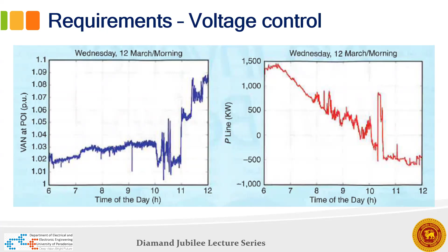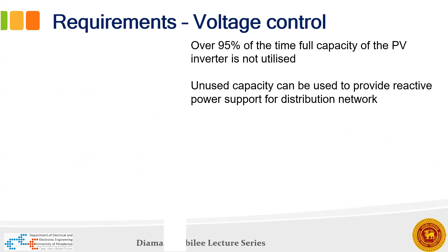You can see that somewhere around 12 noon, the voltage has almost reached 1.09. This is in Germany, so you definitely need good voltage control methods if you are going to operate mini grids. But it is there on our inverters. Remember, our inverters are operating at full capacity only a little time of the day; the remaining time, there's plenty of capacity remaining.